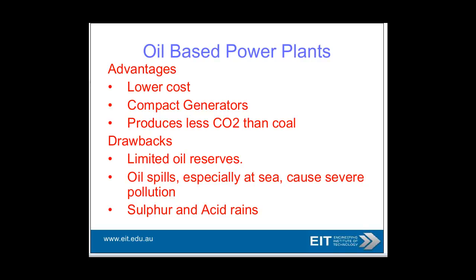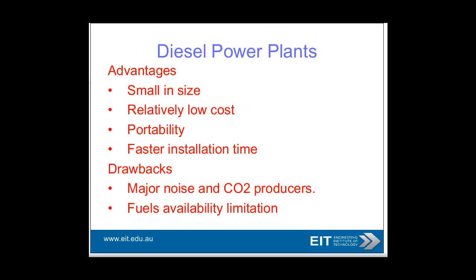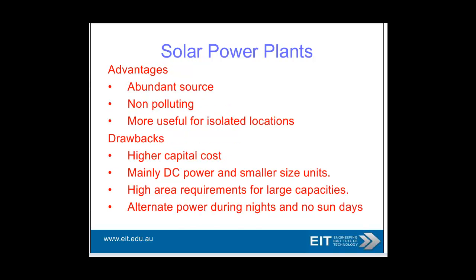Quite an investment in high capital. Oil-based power plants have lower cost and are compact. The problem is you could run out of oil, and they're not very attractive because of environmental pollution. You also get some problems with oil with a high sulfur content, giving a polluting effect. Diesel power plants are small in size, low cost, portable, very quick to install, very proven technology. Plug and play. Major noise and carbon dioxide producers. They make quite a bit of noise, although you can suppress a lot of it, and there could be a fuel limitation. Not going to worry about the other power plants here.